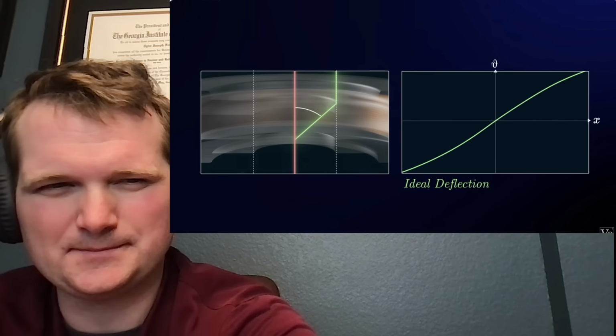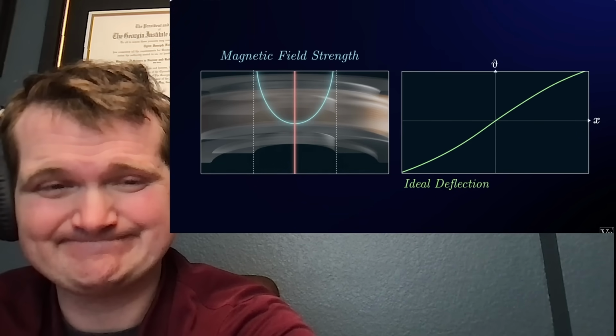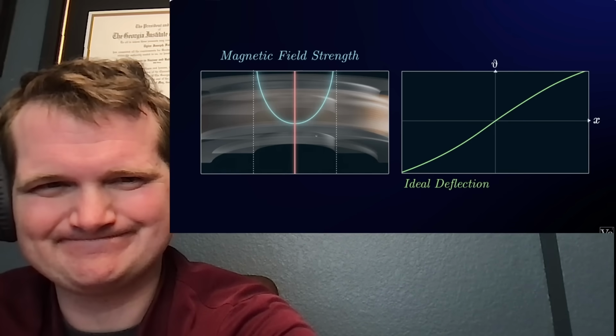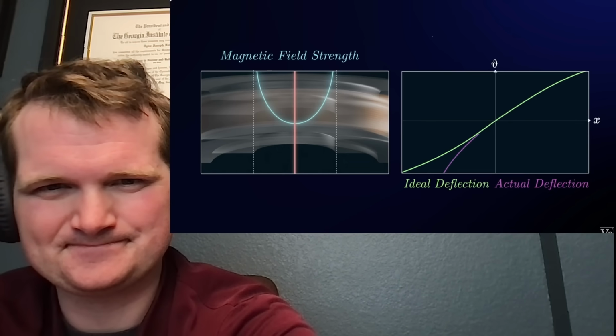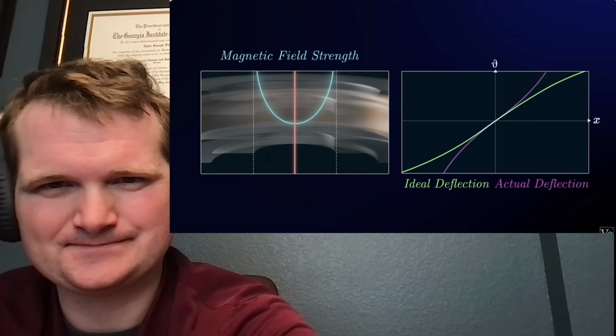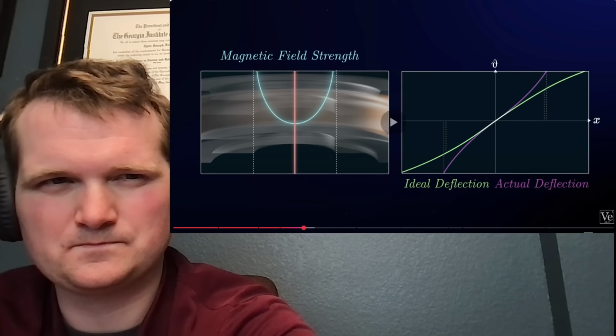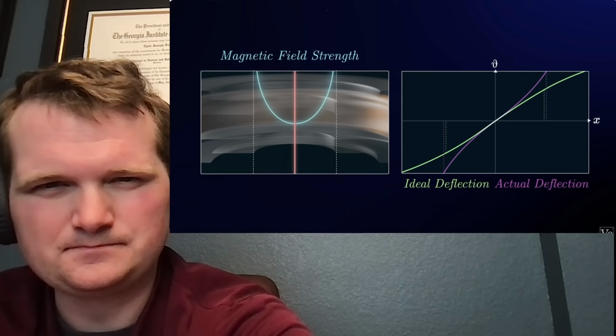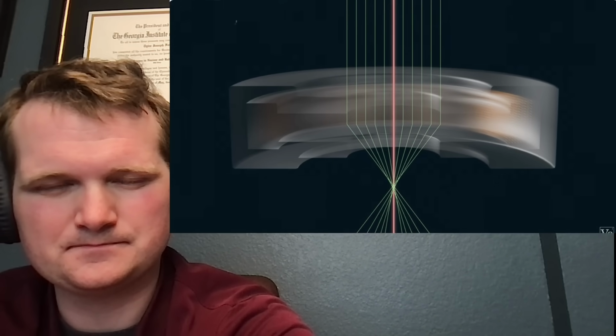The problem is that the magnetic field doesn't scale linearly. It's much stronger near the edges of the magnet. So if you plot the curve for the actual deflection of the electrons, you'll see that the magnetic field over-deflects the electrons further out. Their angles are bigger than they should be, so they end up focusing before the rays in the middle. And as a result, the focus is spread across the optical axis instead of being contained in a single point. The blur starts out around the edges of the image, but it gets worse the higher the magnification.